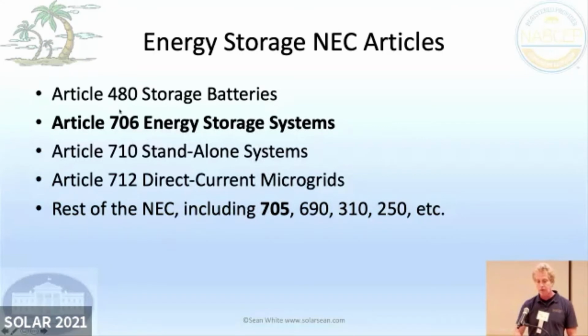Energy storage system 706, we're usually talking like there's no UL 9540 listed energy storage system. That's the listing that we use for these that does not come with an inverter. So it's almost like if you wanted to be really strict at interpreting the code, you can't even have a DC energy storage system, because there's no listed one. That could change, but just nobody's gone to the trouble to list it that way.